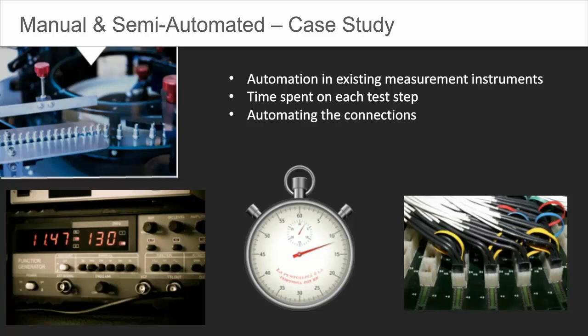First, purchase a new meter with a programmable interface to replace the one that was not automatable. Second, provide configurable automation test steps associated with each type of measurement instrument. So then the operators could go in and create a sequence of test steps to set up each instrument and record the resulting measurement. This sequence of steps could be saved and recalled for each product being tested so that the instruments could be automatically configured and the steps could be automatically sequenced through.